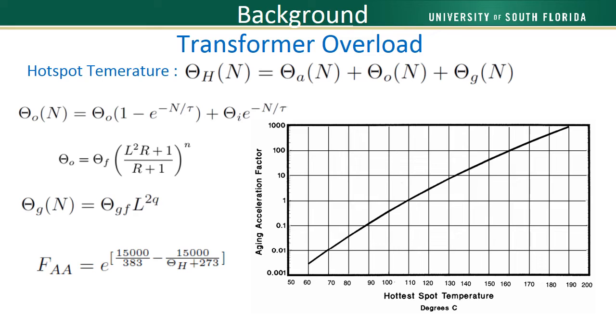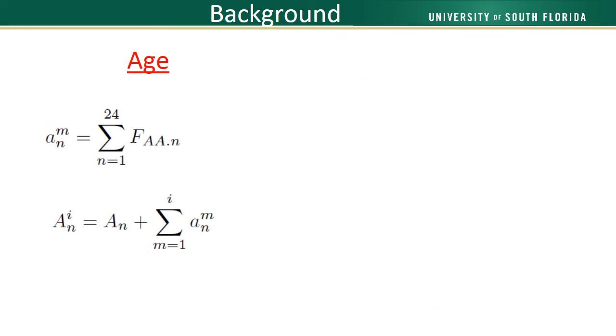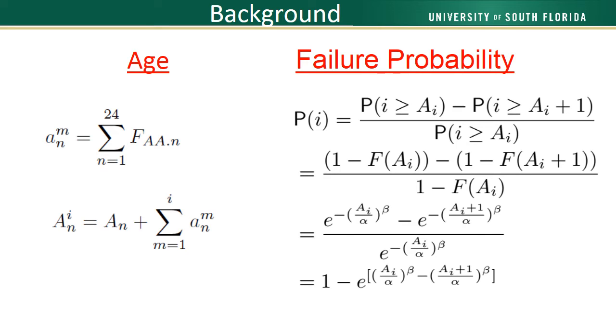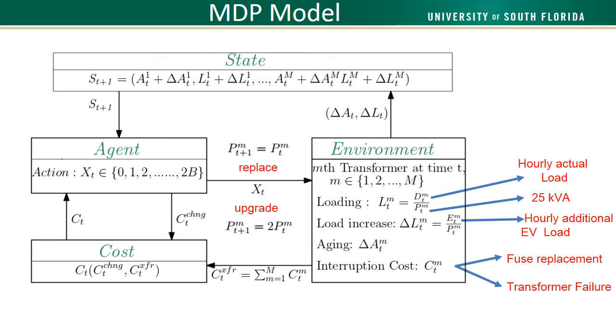IEEE recommends 20.55 years of effective life for a distribution transformer. So we can calculate the effective age of a transformer by adding each hour of effective age accumulated through serving the load. We use a Weibull hazard function to generate the aging related failures. The probability of transformer failure during the ith day is P_i, which depends on the effective age A_i of the transformer. Alpha and beta are respectively the scale and shape parameters of the Weibull distribution, whose values can be modeled from existing literature. We apply a Markov decision process for our problem.